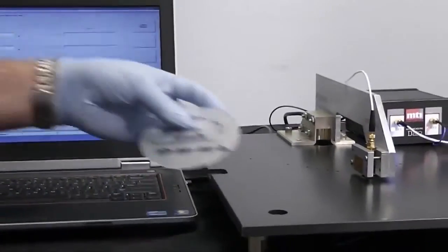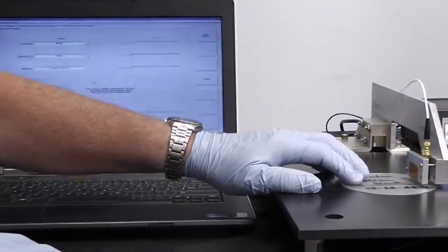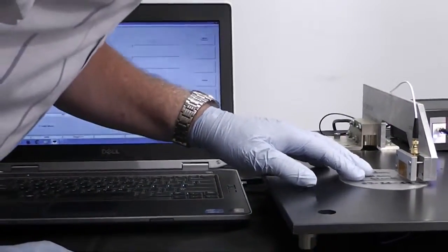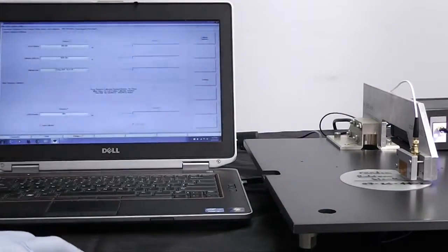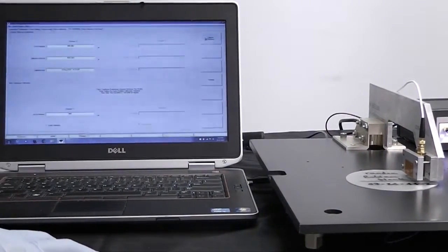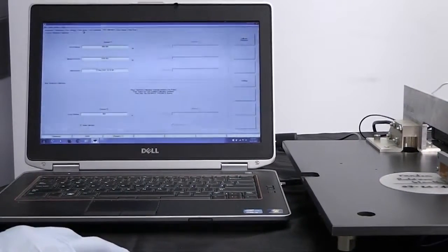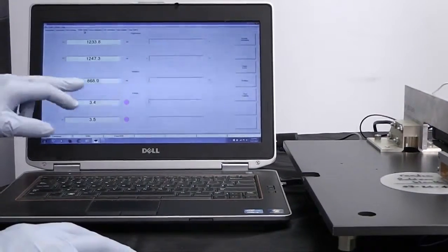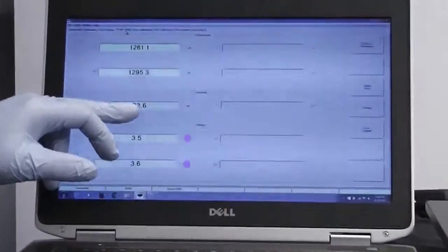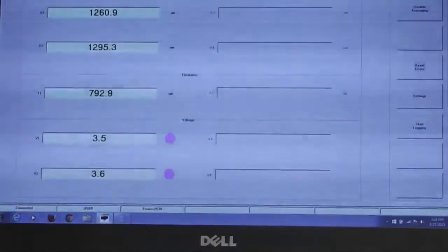We're then going to go back to the thickness calibration window. We're going to put our first wafer, which was 868 microns, in between the 2 probes. I have to make sure I get that centered correctly. And then we're going to hit calibrate thickness. Once we do that, we're all set, we're good to go. We go back to reading thickness, and you can see that I'm reading the thickness of the wafer, 868. Let's take a look at this one here, which is 793. We're going to slide that under there, and we're reading within 0.2 microns of 793, 792.8.